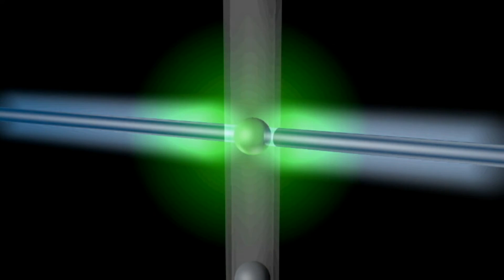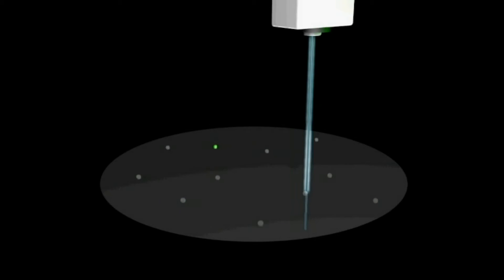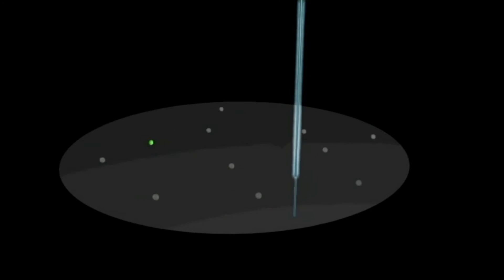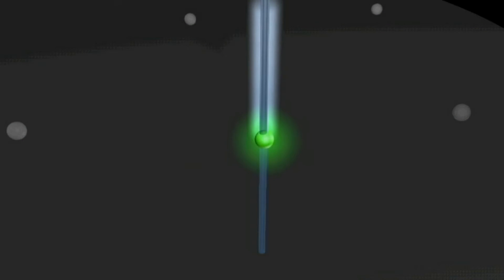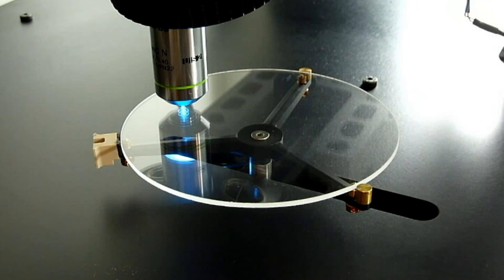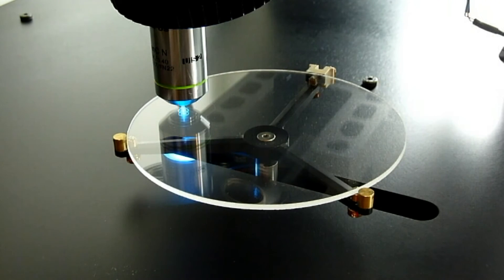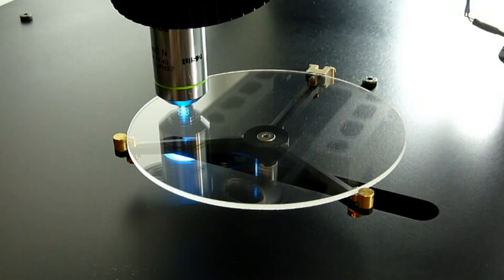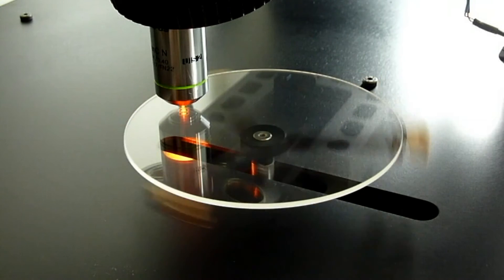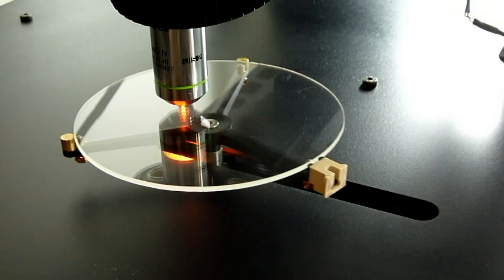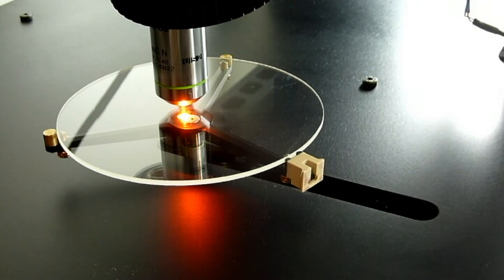In flow cytometry, cells are guided through a laser detector by a fluent string of liquid. By Cytotrack, cells are guided through a laser detector, not by a fluent string, but by the mechanical disk that rotates in front of the laser detector. After the primary scanning, the Cytotrack scanner functions as a standard fluorescent microscope. The primary scanning pinpoints a number of hotspots. During the analysis, each hotspot position is revisited and the target cell is analyzed by fluorescent imaging.